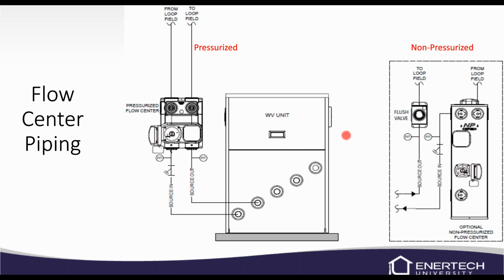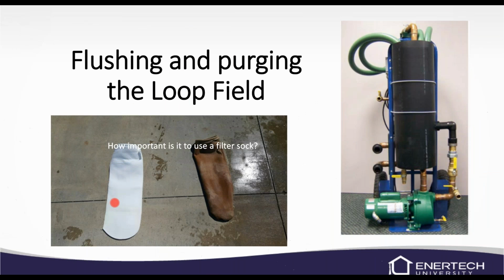We kind of covered this already, the piping. Just remember, always install your strainers. When you're flushing, this is a flush cart over here to the right. We have a newer flush cart now. It's got a sight glass on it, so you can see the level in the tank. But I would always recommend that you use these filter socks when you're flushing. They'll go right over this return line that hangs down into the tank.